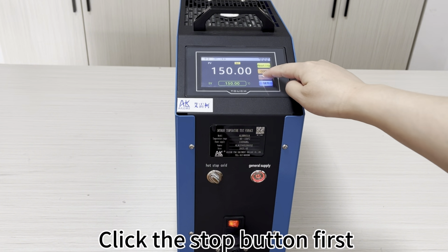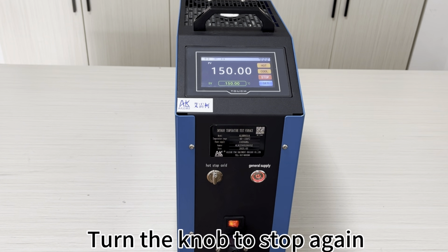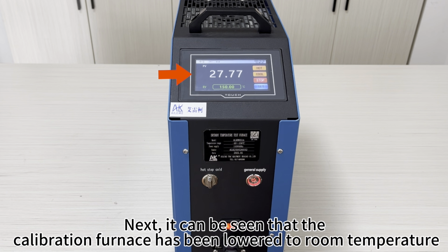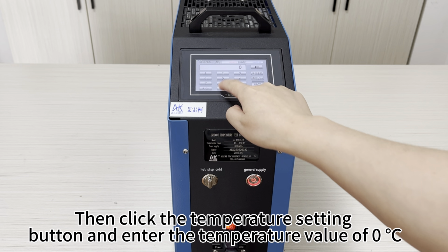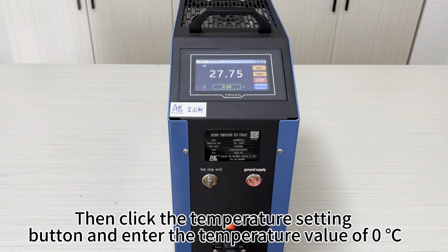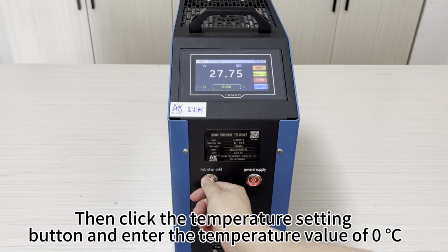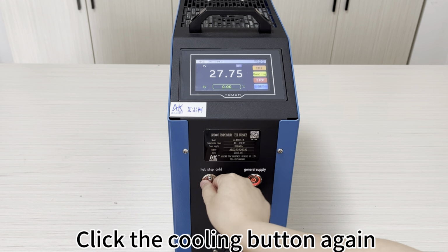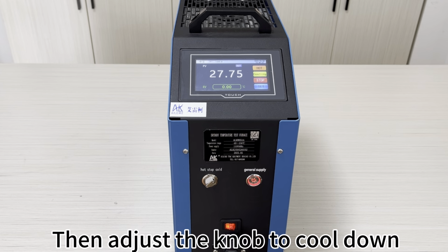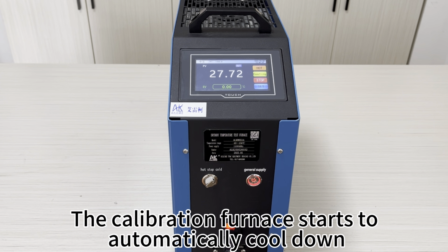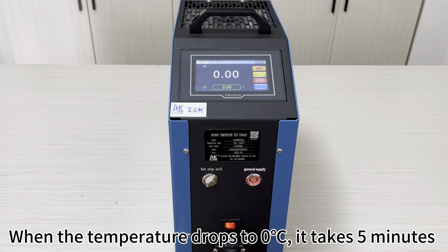Click the stop button first. Turn the knob to stop again. Next, it can be seen that the calibration furnace has been lowered to room temperature. Then click the temperature setting button and enter the temperature value of 0 degrees Celsius. Click the cooling button again, then adjust the knob to cool down. The calibration furnace starts to automatically cool down. When the temperature drops to 0 degrees Celsius, it takes 5 minutes.